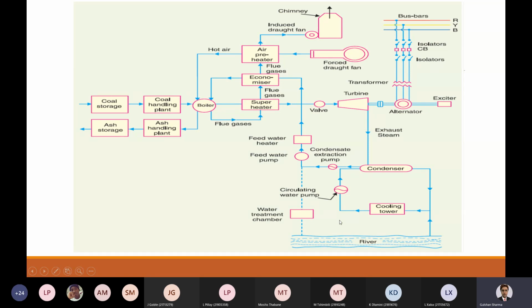And there's one more concern. I don't know if you know, there are three types of turbine. First is the high pressure turbine, another is the intermediate pressure turbine, and third is the low pressure turbine. I don't know if the book gives the detail of the three types of turbine. It's not only one turbine where the steam falls. First it will fall into the high pressure turbine, then into the intermediate pressure turbine, and then finally into the low pressure turbine. The three turbines are coupled with a common shaft and bearing, and then they are coupled to the alternator.